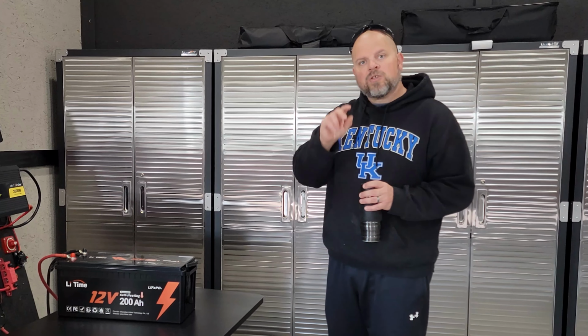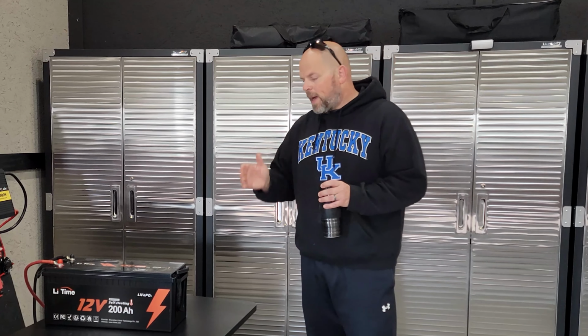That's two panels, 400 watt Aptos solar panels that are bifacial. We're not getting much gain the way they're set up, so 400 watts is completely within reason of the recommendation for solar input on this MPPT. On 12 volts, the maximum is 900 watts. So if you're hooking up a 24, 36, or 48 volt system, which this can handle all of those, make sure you understand the maximum wattage your array can feed into the MPPT.